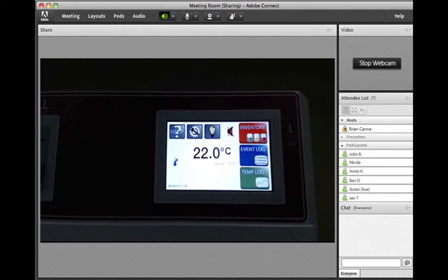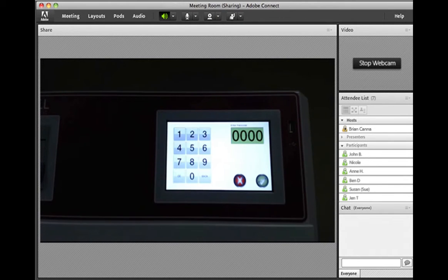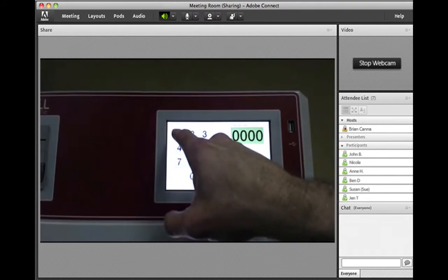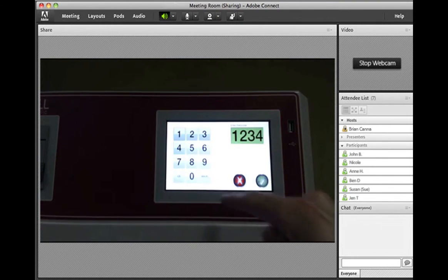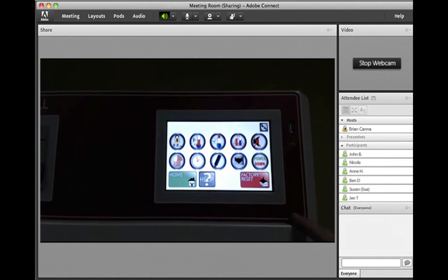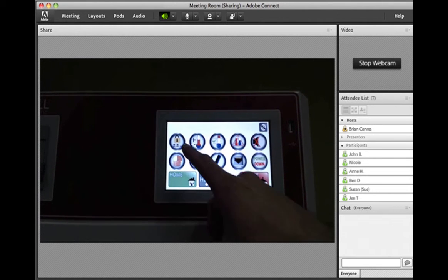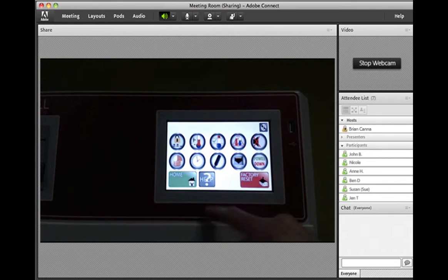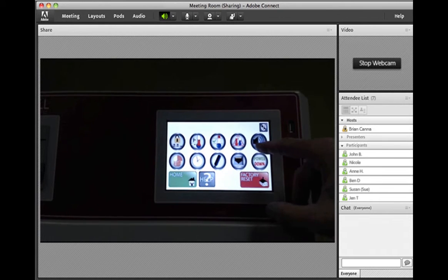If you do want to change the set point or change some advanced configuration, all of that is behind the setup menu, which is password protected. The default password is 1234. You can change this, obviously. And now we see we have a nice array of icons that you can configure. So this is how you would change the password. This is how you would increase or decrease the set point. This is how you would check your calibration. This is how you set your high-low temperature alarms. This is how you would turn off or on the speaker on the system for all the alarms.